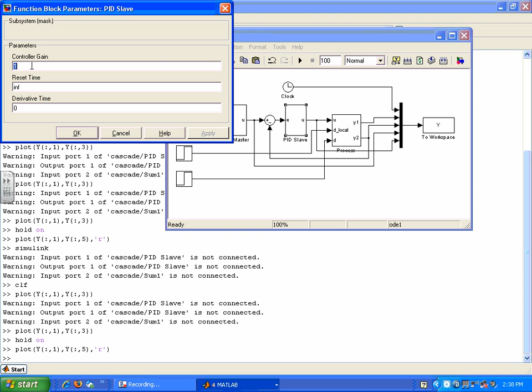So I go to my library, and from the relay, it's clear how you use the relay feedback test. So I delete this, I put my stuff back in. Did it get connected? No. Yeah, now it's connected. And I'm going to use a controller gain of 3.5, right? Notice that I didn't have to do a step test. I just operated the process around steady state and got sustained oscillations around the steady state, right? So now my slave loop is tuned.